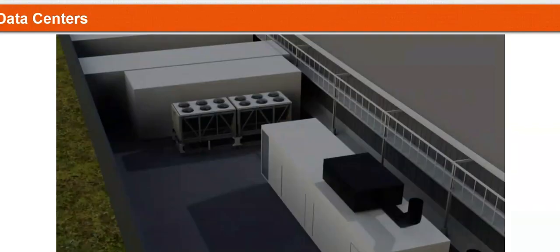But before that, one of the main hot topics lately in many states across the US and Canada is data centers. These are big buildings that have a lot of equipment to keep those servers cool, especially the ones that maybe are not using adiabatic coolers yet. Depending on where it is, if they put them in Texas or Phoenix with very harsh environments, you're going to need a lot of equipment plus backup power, additional to all the air handling units to bring air in to cool them off, and you have hundreds of these pieces of equipment close to residential. Those are a good example of sites that could use noise control solutions without exception.